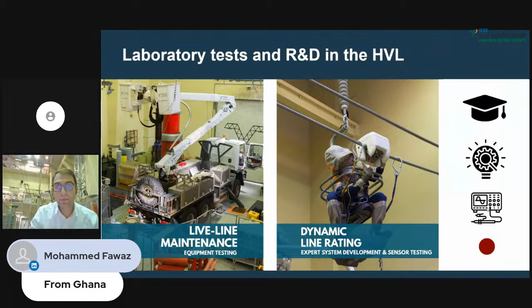As Balint mentioned, we are an accredited laboratory, and this is important because in case of live working and vicinity work, the key word is safety. This means that the tools and personal protective equipment need to be tested regularly on a yearly basis. In this laboratory, we can do such tests on medium voltage and also on high voltage level.